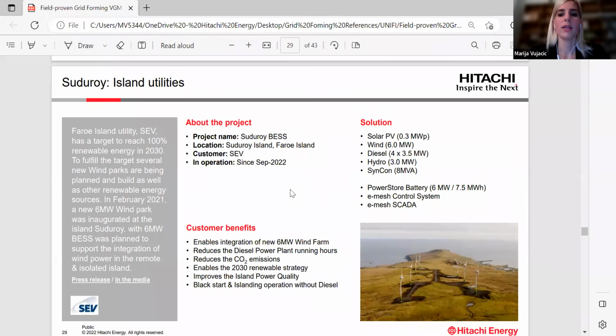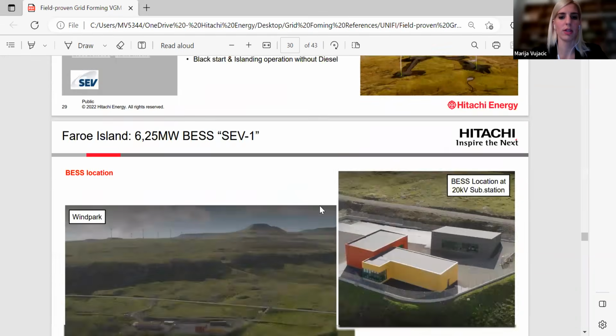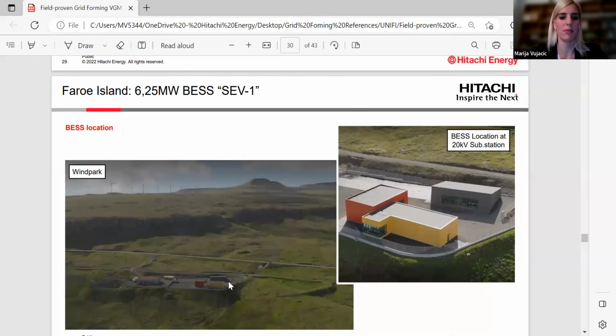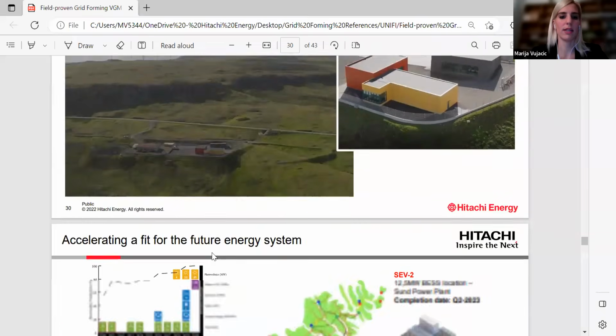Here we deployed a PowerStore battery system of 6 megawatt, 7.5 megawatt hour size, and as you can see here, other generators are solar PV and wind. There are some diesel generators together with a relatively small hydro plant, and a synchronous condenser was installed at the same time as the PowerStore battery system. The EMesh control system, a distributed control system, was also installed to ensure seamless operation of the battery energy storage system with the wind farm and the rest of the network. As you can see here, the battery energy storage system is installed in close proximity to the wind farm, but the rating of the wind farm and the battery energy storage system in this case is of a relatively similar size.